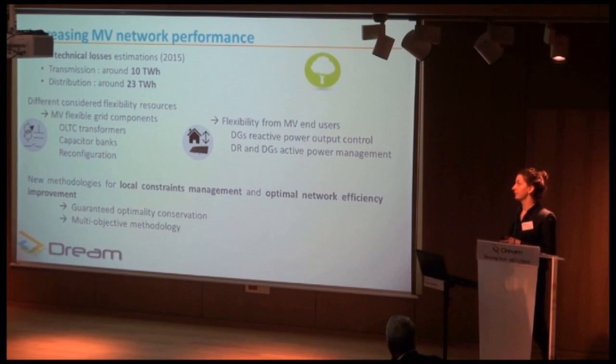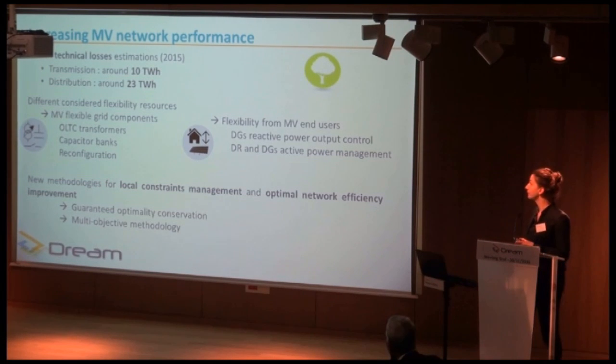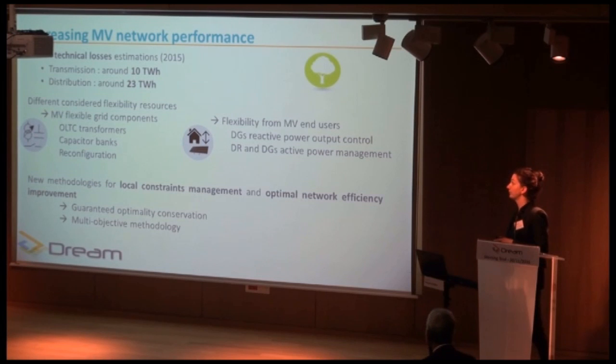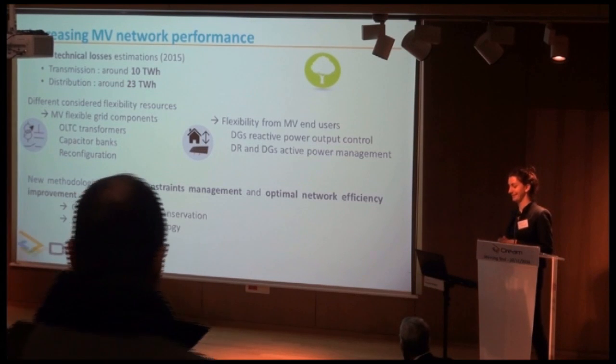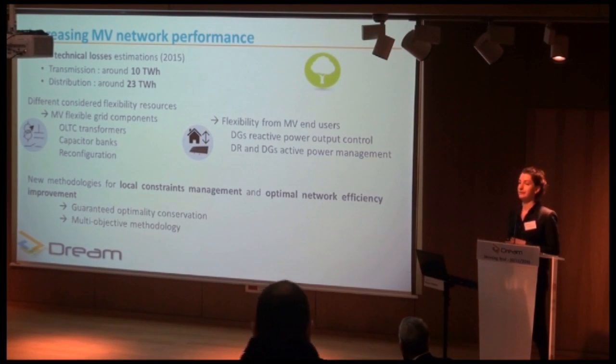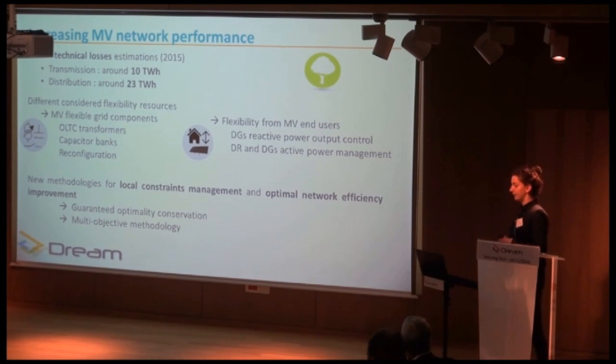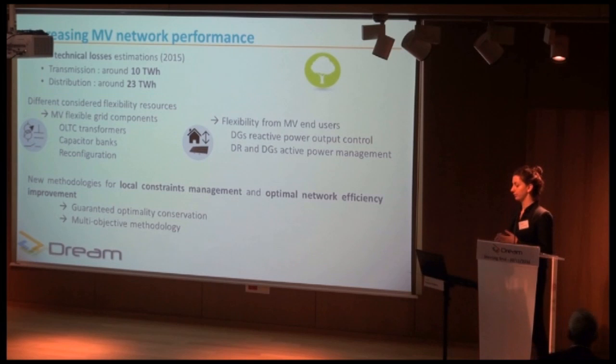And finally, I also created some methods for increasing the MV network performance because we know that the French technical losses in 2015 were about 23 terawatt-hours in the distribution network, so it's quite a lot. And so I created a method which considers different flexibility resources, such as the flexibility of the grid, with the OLTC transformer, the capacitor banks, the reconfiguration, but also the flexibility from the MV users. And I created new methodologies for local constraint management and network efficiency improvement.